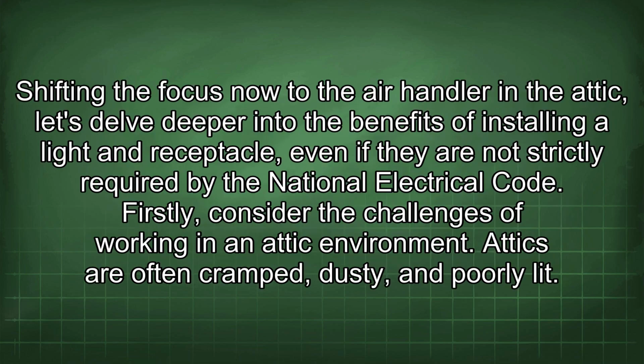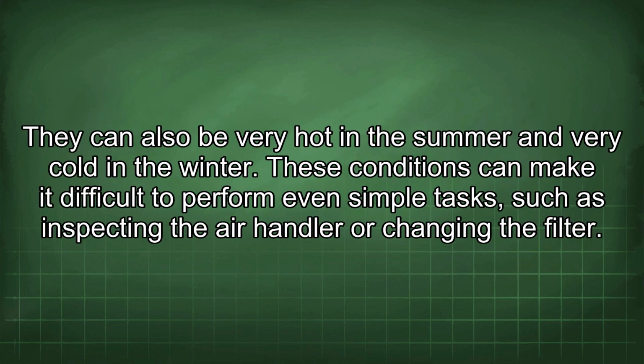Shifting the focus now to the air handler in the attic, let's delve deeper into the benefits of installing a light and receptacle, even if they are not strictly required by the National Electrical Code. Firstly, consider the challenges of working in an attic environment. Attics are often cramped, dusty, and poorly lit. They can also be very hot in the summer and very cold in the winter.